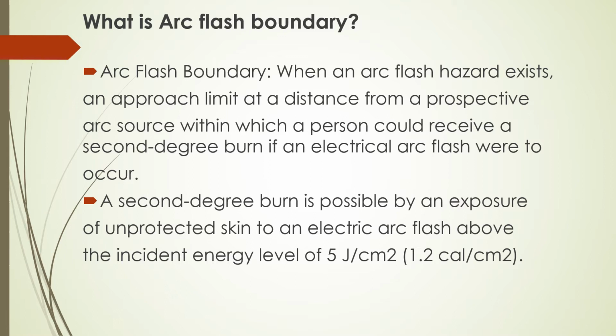What is arc flash boundary? Arc flash boundary: when an arc flash hazard exists, an approach limit at a distance from a prospective arc source within which a person could receive a second degree burn if an electrical arc flash were to occur. A second degree burn is possible by an exposure of unprotected skin to an arc flash above the incident energy level of 5 joule per centimeter square or 1.2 calorie per centimeter square.